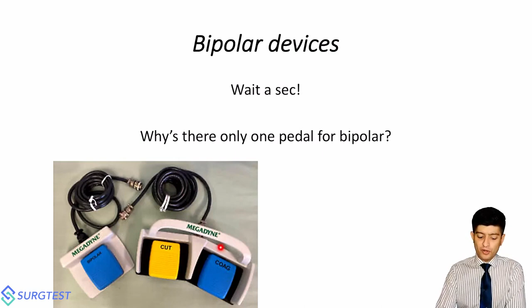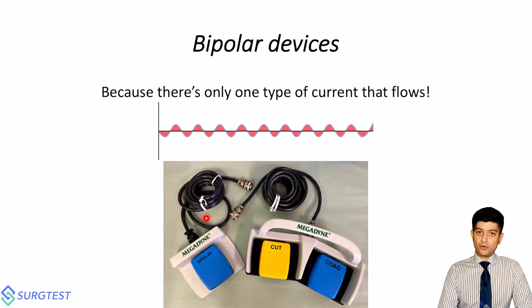So wait a second, there is only one pedal for bipolar, correct? There will always be a cut and coag pedal for monopolar, but for bipolar there is only one. There's a reason for that, because there's only one type of current that flows in bipolar devices, and that is this: a low voltage continuous waveform current with a duty cycle of 100%. So note that a cutting current is flowing through a bipolar device, but the color of the pedal is blue. Doesn't make sense, right? It's like a facepalm moment over there.